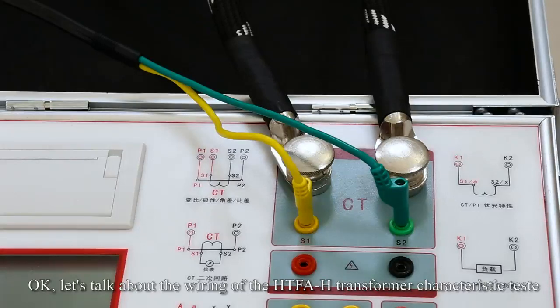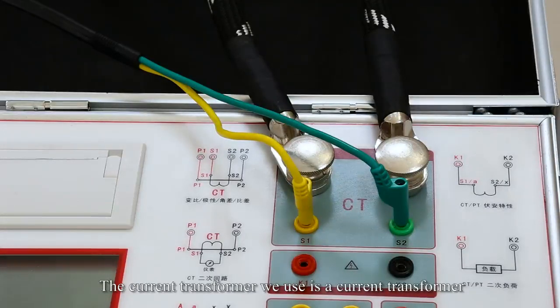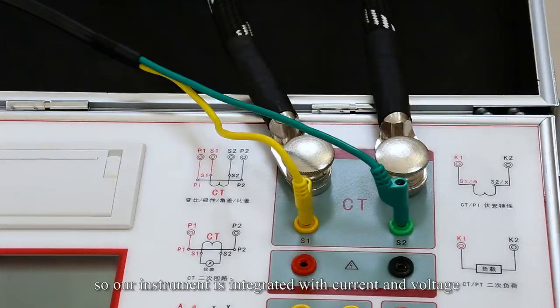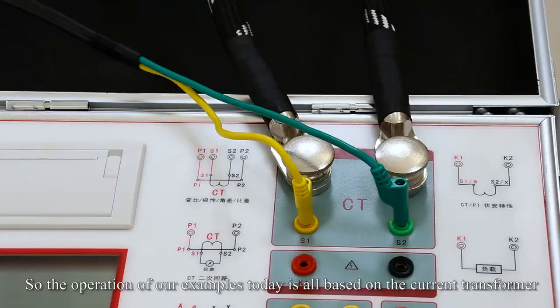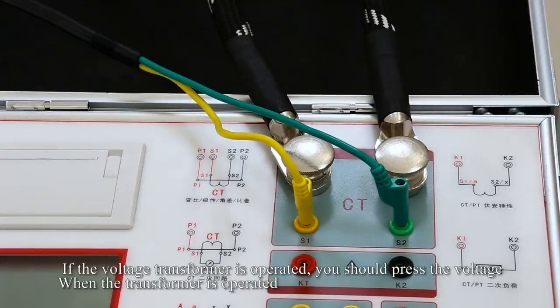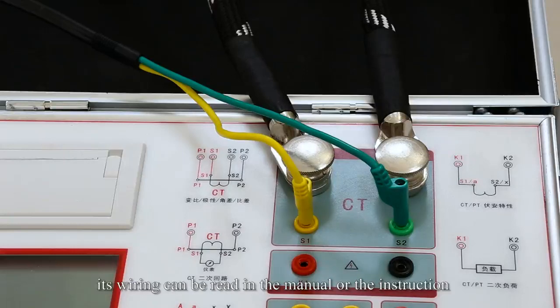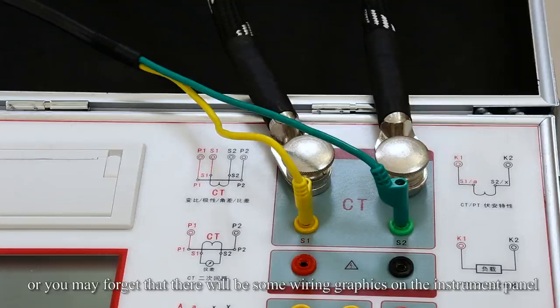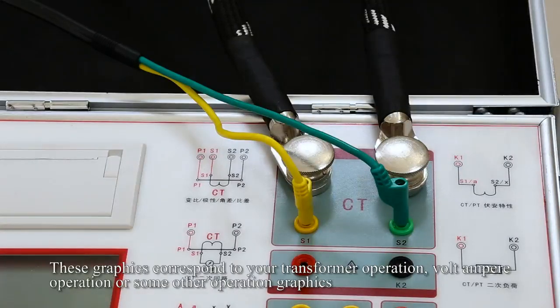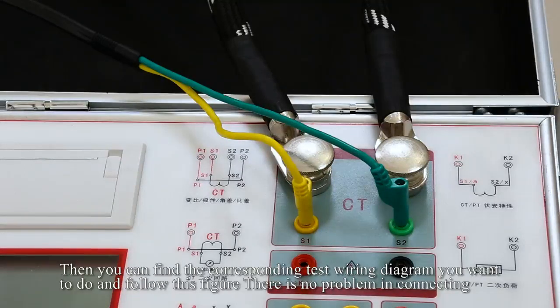Okay, let's talk about the wiring of the HTFA-II transformer characteristic tester. Our instrument is integrated for current and voltage, and we are using a current transformer now, so all the examples today are based on the current transformer. If you operate a voltage transformer, you should press the voltage option. The wiring can be read in the manual or on the instrument panel, where there are wiring graphics corresponding to the transformer operation, volt-amp operation, or other operations. Find the test wiring diagram you want and follow the figure, and there is no problem in connecting.